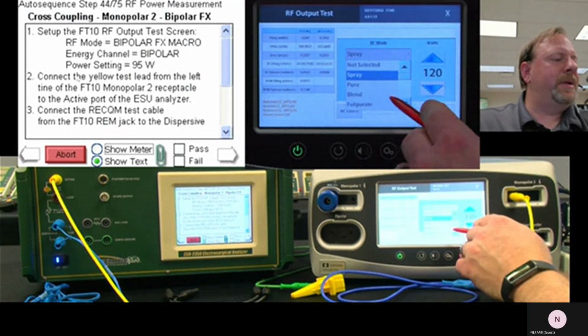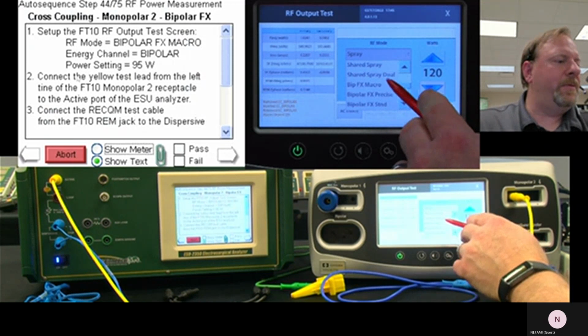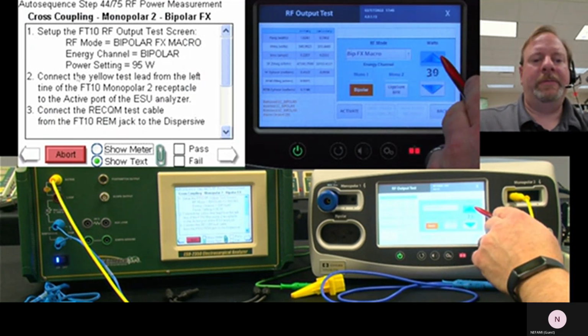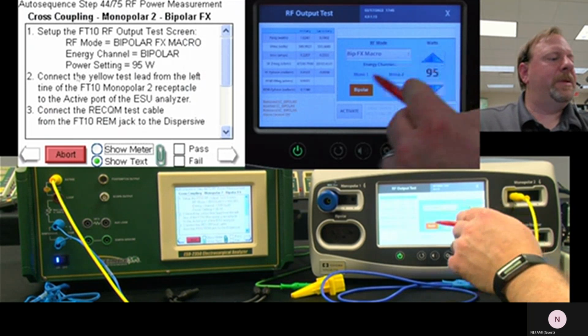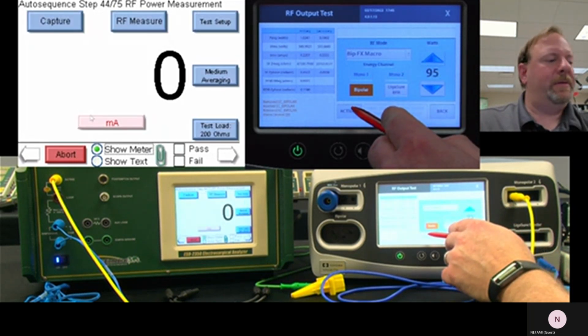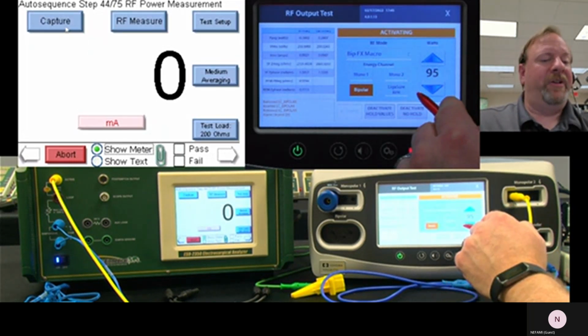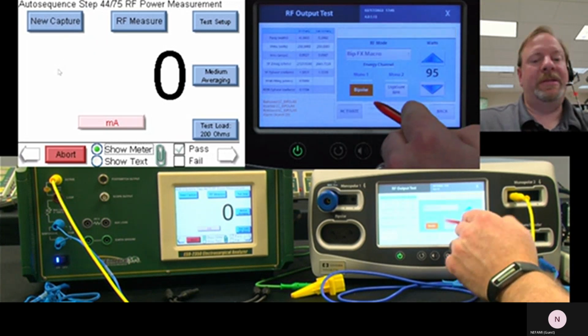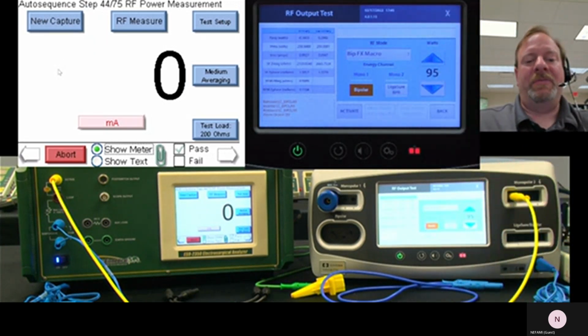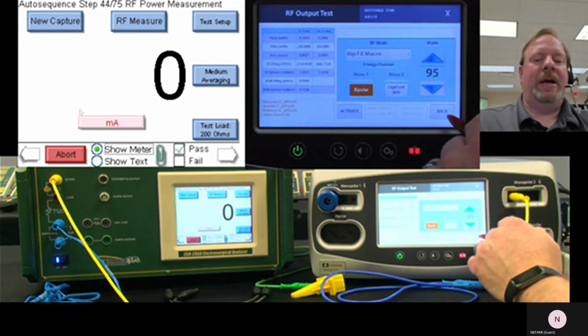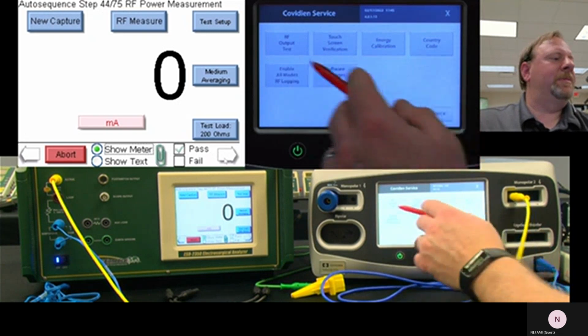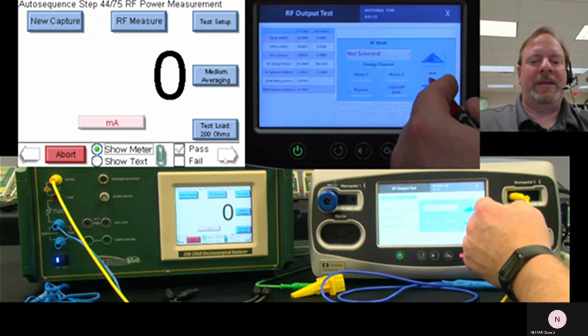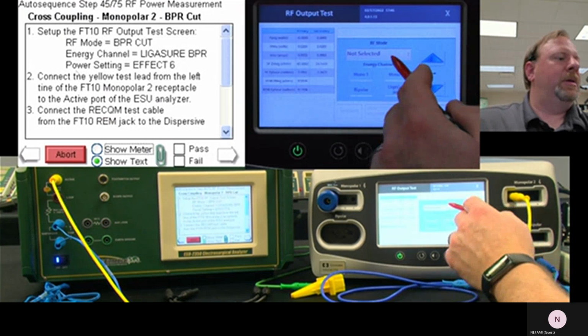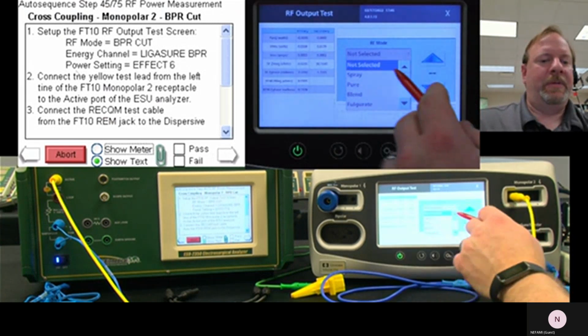We're still measuring on monopolar 2, but we're activating bipolar macro. Max power. How much energy comes out the wrong port? Let's find out. Very little. That was the same thing with monopolar 1, so that's a good thing. Now, as you run these and you get used to this, if you get something that's not really low, even if the limit is 100 milliamps, you might want to question whether something's going wrong with that generator.